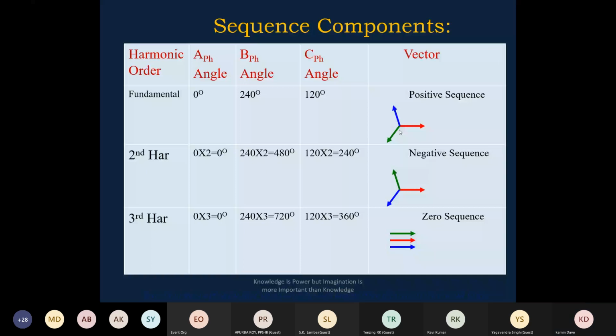Normally, during transformer charging, we can say the second harmonic component is present at, for example, 40 to 50%. You see, the negative sequence component will be high, and the transformer inrush current is not a balanced vector; it is an unbalanced vector. It is normally a unipolar or distorted waveform. That is why we say it is an inrush current. It's not a regular, normal current.